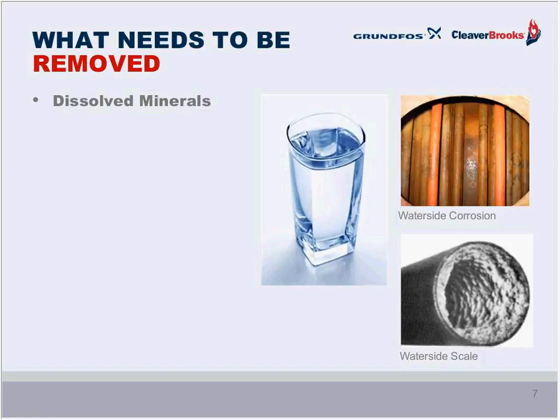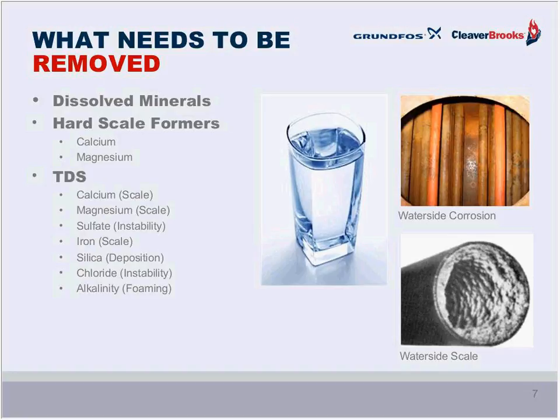So these are the minerals and gases which need to be addressed through proper dosing in order to alleviate or mitigate the problems that I mentioned. The first is hard scale formers, the calcium and magnesium that precipitate out of the water. You can't see it, but it's there. And TDS, including the calcium and magnesium that I mentioned before, which form the scale. Then you also have sulfite, which becomes sulfate and causes instability of the water level in the boiler itself. You have iron that causes scale. You have silica that deposits and reduces the heat energy transfer rate. You have chlorides that cause instability. And you have alkalinity that causes foaming.